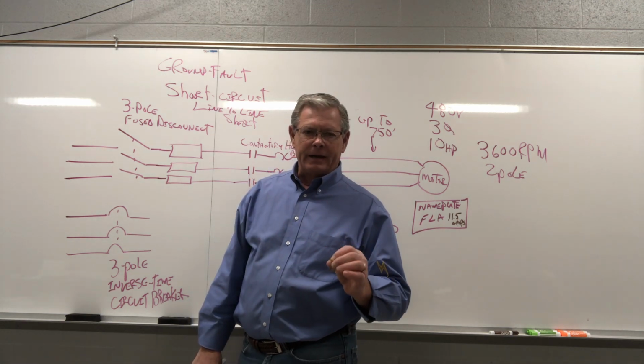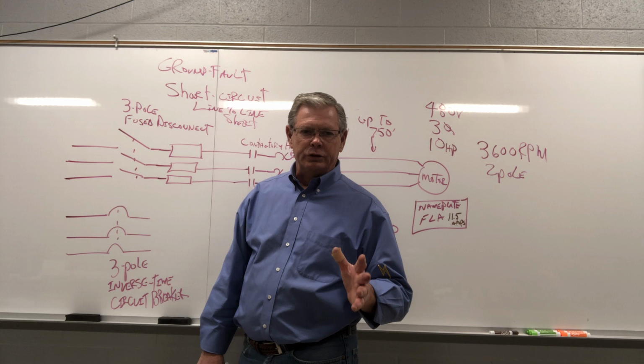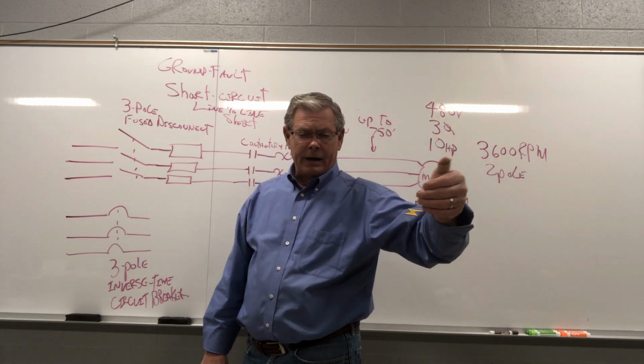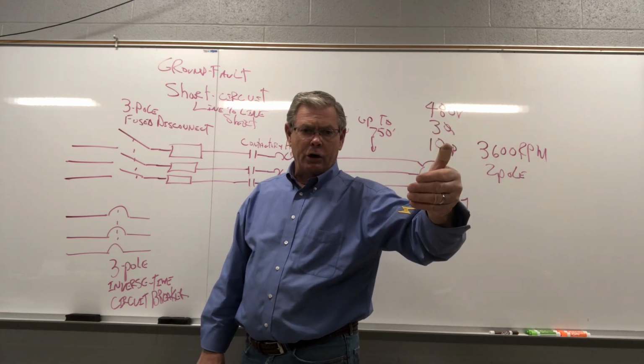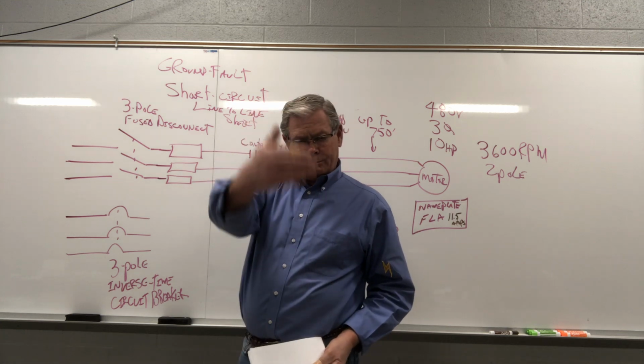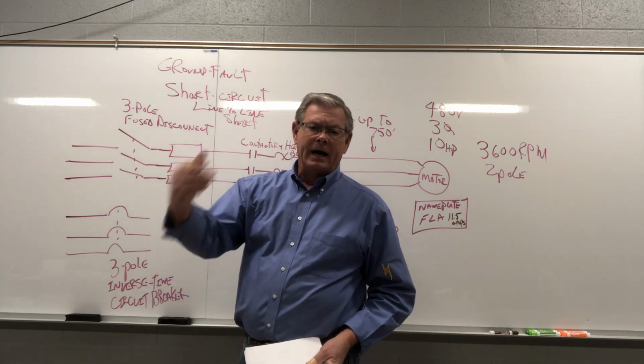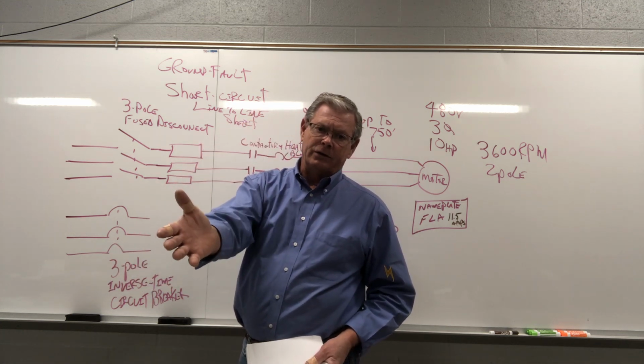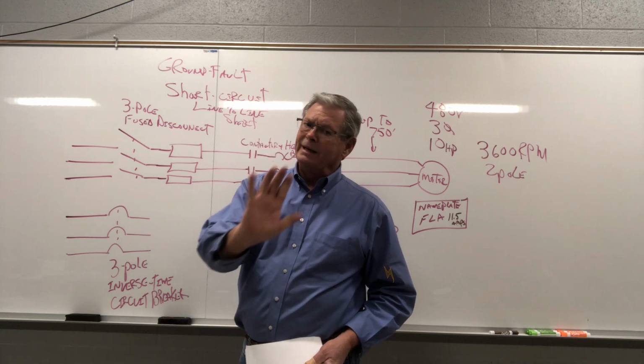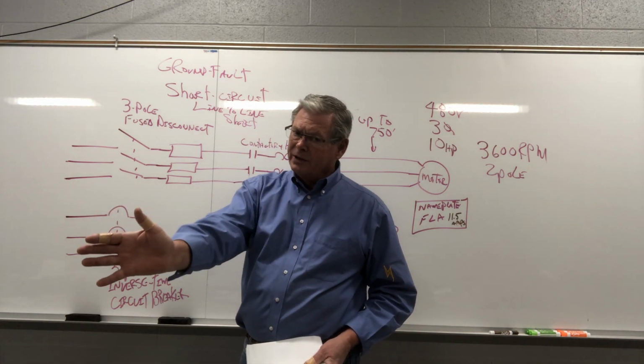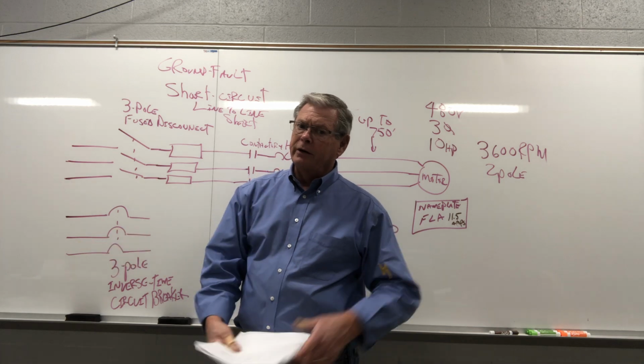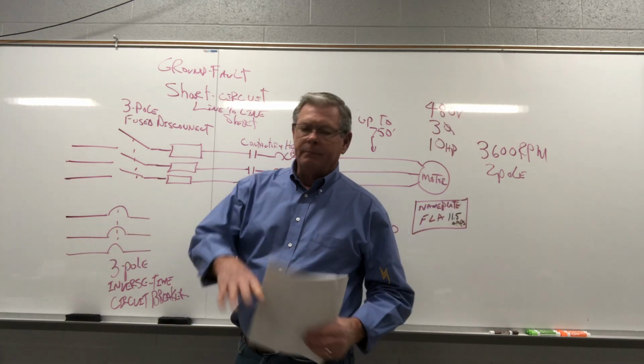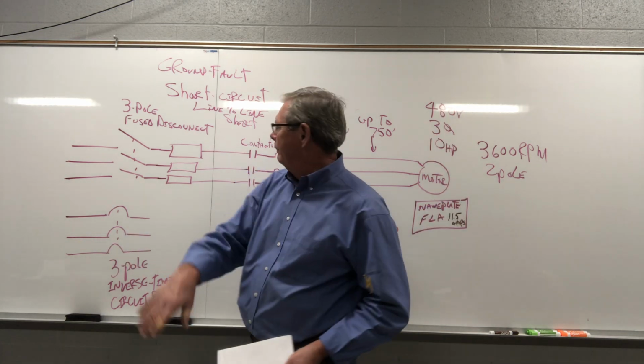This is the same layout as you have for your home power distribution panel. You've got a 200 amp breaker or 100 amp breaker coming into your home, and then that's going to break off and feed different areas of your house, like the 15 amp breaker that feeds your living room. Okay, you got to have a way to disconnect your living room and also protect that living room circuit from that 200 amp breaker. Motor control center, same thing.